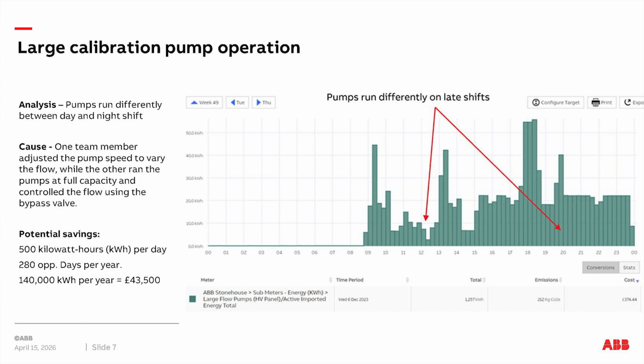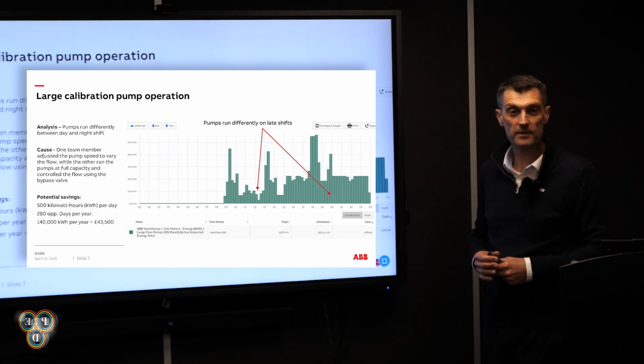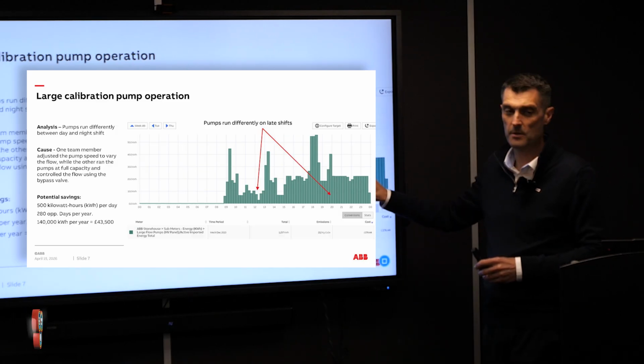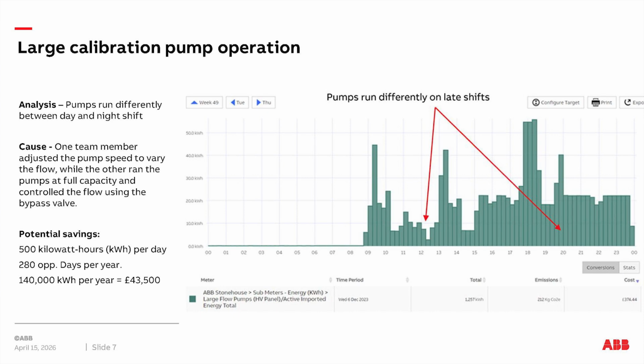What we noticed was the pumps were running differently between the day and night shift. This is a single day, 6th of December 2023, with 1,257 kilowatt hours of usage - a fairly high consumer, costing maybe £375 for a day's energy usage, so whatever it was doing must be quite high value. But the pattern of usage is different: there's a lot more peaks and troughs in the morning shift, while the afternoon/evening shift is fairly solid.